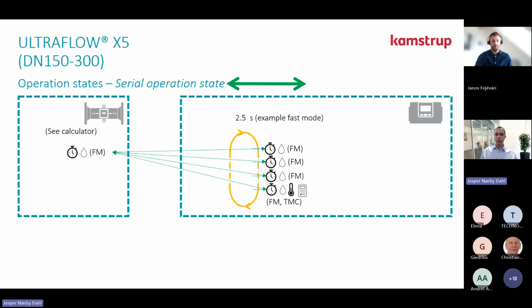Meaning the calculator will ask the flow sensor, please perform a flow measurement and return it back to me. And it will do this every 2.5 seconds, sending a signal to the flow sensor, telling the flow sensor to make a measurement and return it back to the calculator. And after 4 of these, it will calculate the energy in the calculator. So this is what serial communication does.